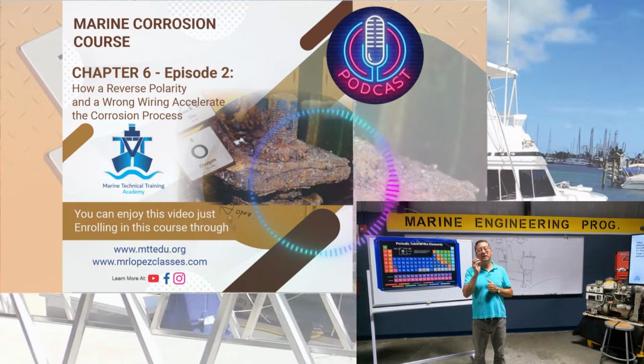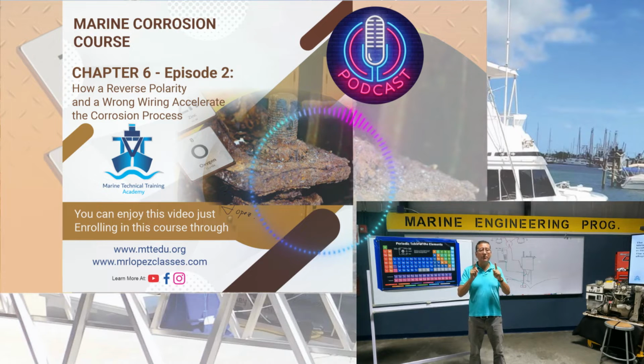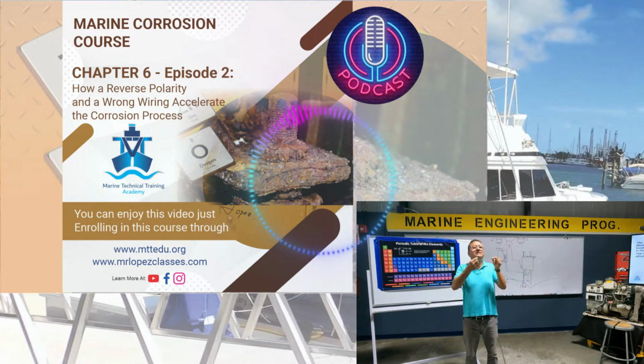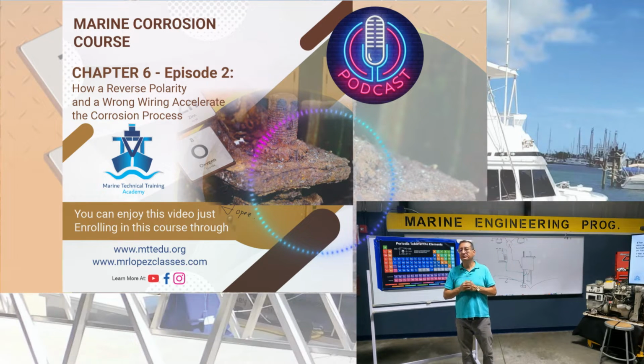But if you have 3 amps, 2 amps constantly, you have a leak, and you need to identify where that leak is. Because that leak of current, at the end of the day, affects all the elements connected to the bonding. Can you imagine all the fittings, all the through holes connected to the bonding, with 3 amps constantly flowing through them for 1 hour, 2 hours, 1 day, 2 days, 1 week?